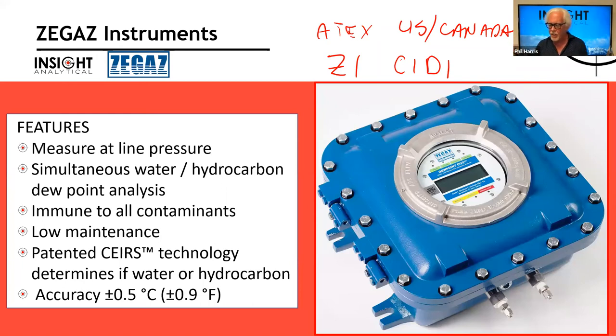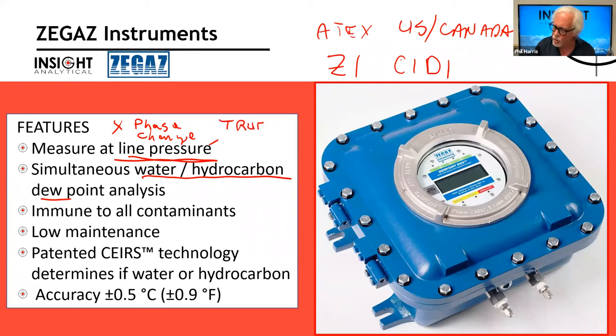The ZEGAZ analyzer is a hydrocarbon and water dew point analyzer, simultaneously measuring water and hydrocarbon dew point, and it operates at the line pressure. The important thing about that is we don't risk the phase change. We don't try to drop the pressure and risk that Joule-Thomson cooling and get a phase change. So it reduces our risk of a phase change, and by operating at line pressure, it can tell us the true dew point of the process line. Remember, we said the dew point temperature is pressure dependent. So if we operate at the same pressure as the pipeline, we're measuring the dew point at the pipeline pressure.